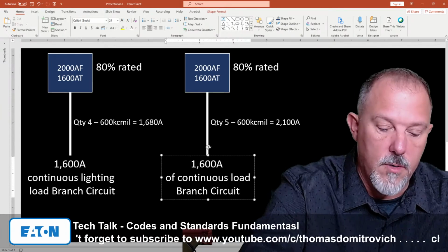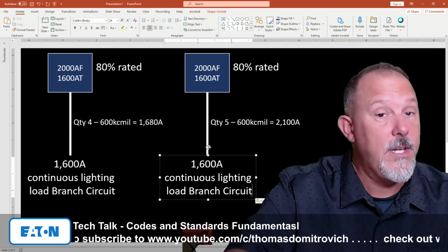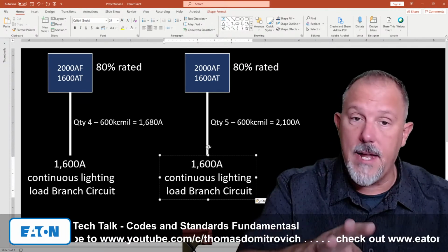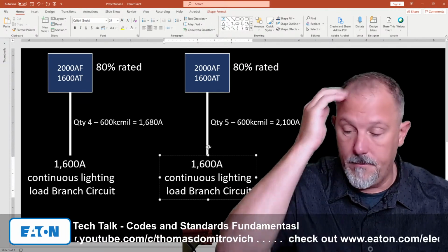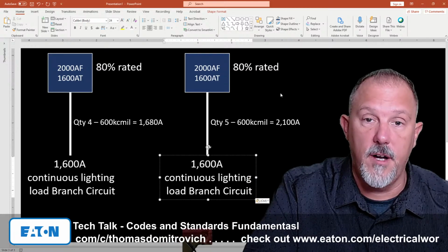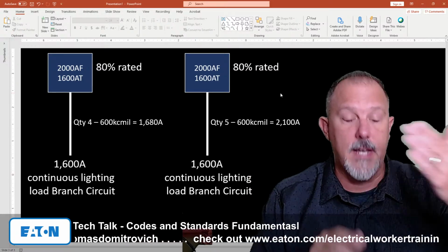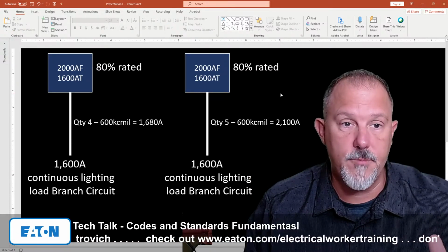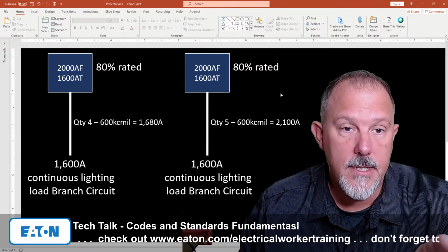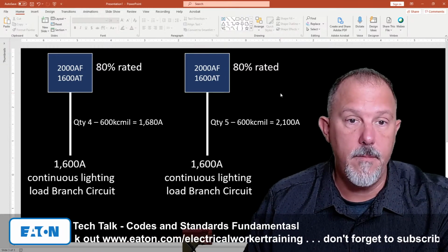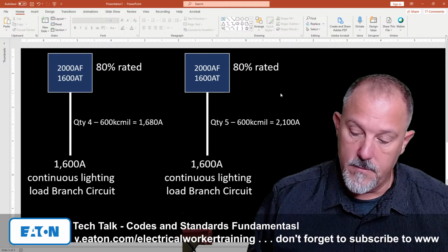So we're getting more and more specific. We know it's a continuous load, 3 hours or more. It's 1600 amps worth of that. I have a 2000 amp frame, 1600 amp trip breaker. Can I put 600 kcmils, 4 of them or 5?